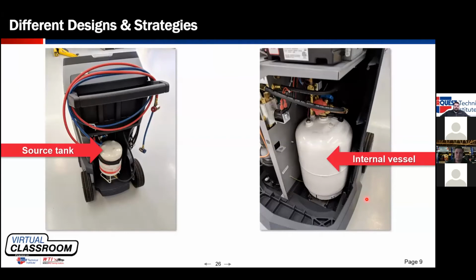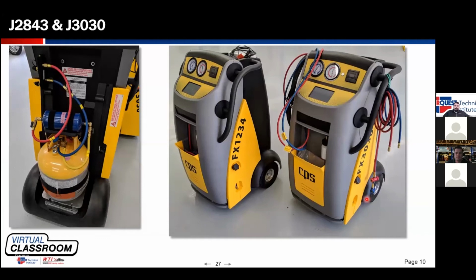Now, there is a second standard for refrigerant recover and recycle equipment for 1234YF. In addition to J2843, which is a machine solely for 1234YF, we have a standard that is called J3030. These are dual machines. Now, what do I mean by dual machine? That means that these are machines that are capable of recovery, recycling, and recharging both 134A and 1234YF. There are currently 3 different versions of J3030 machine on the market. The one that's pictured here, the CPS FX3030, is what we call a back and forth machine.